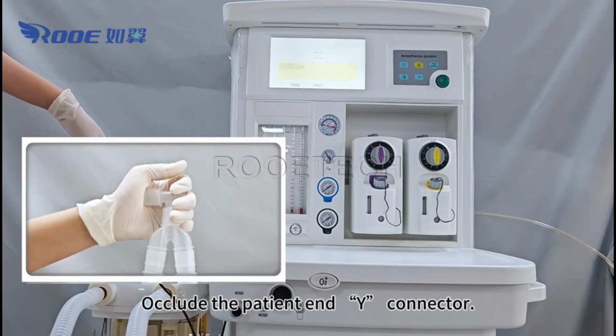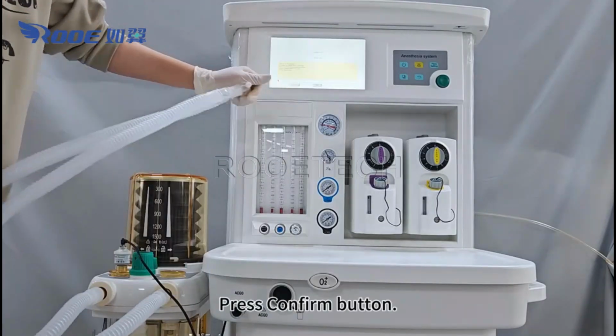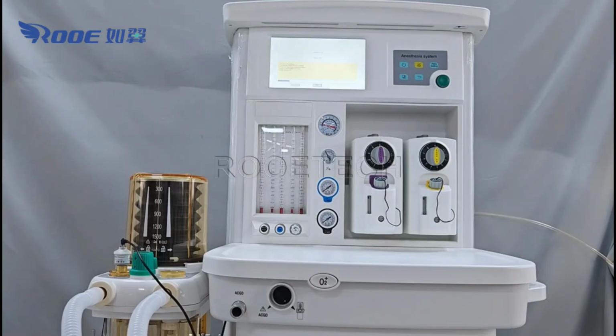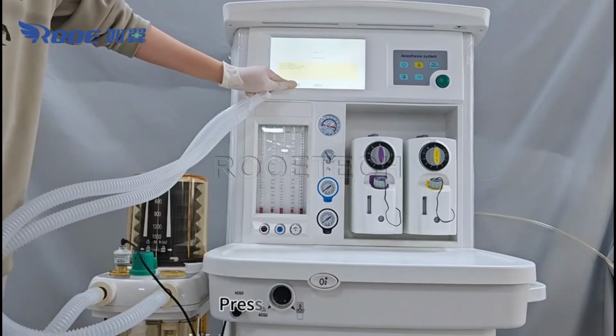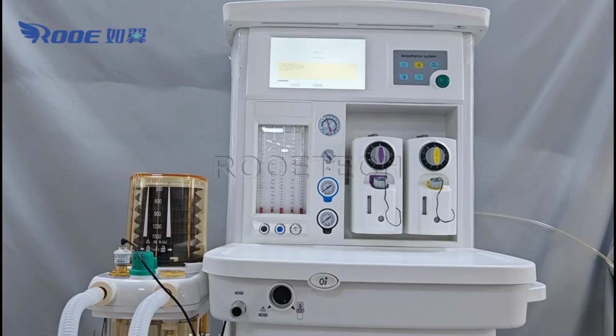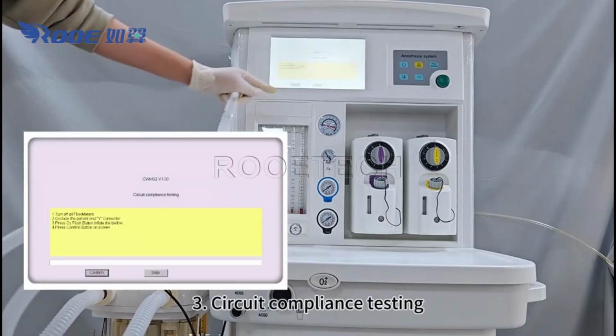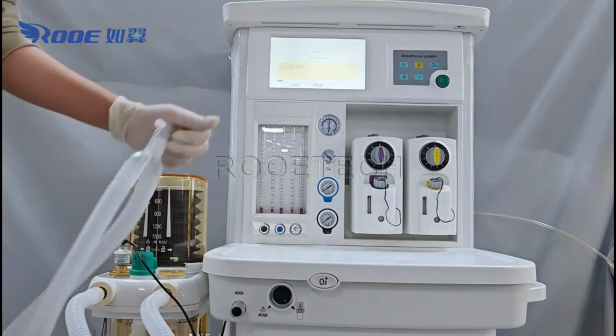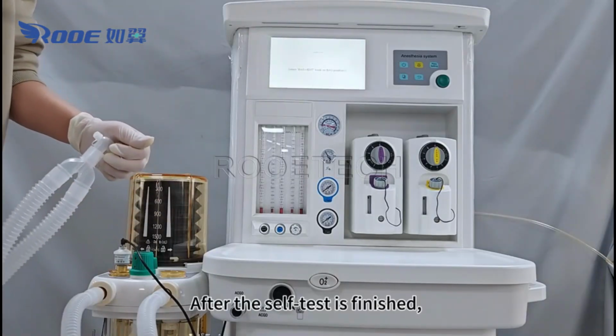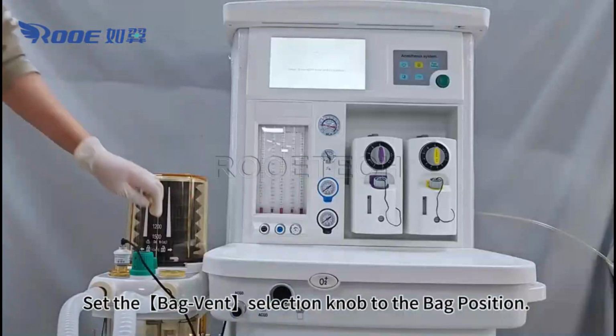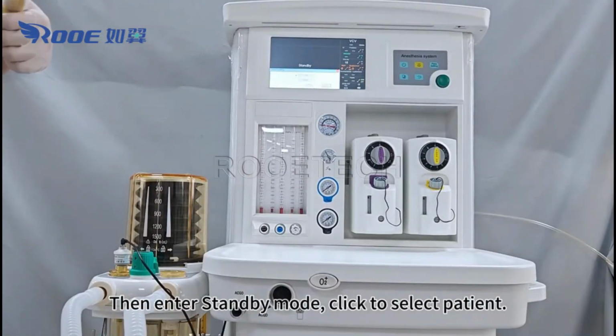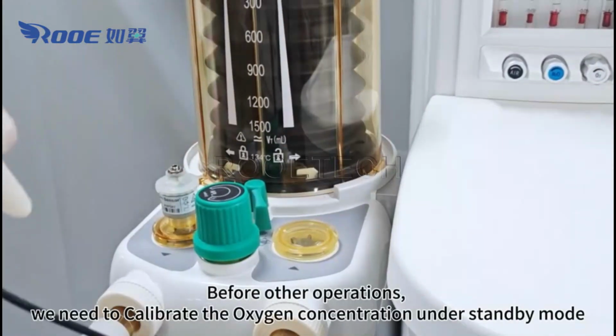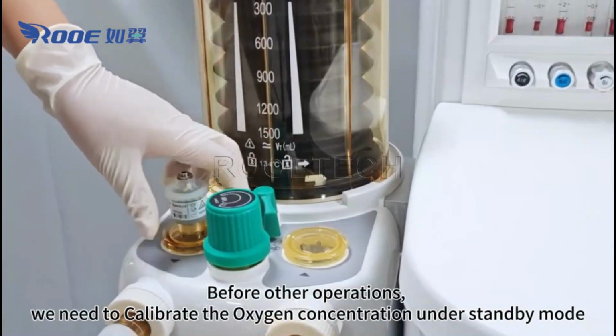Occlude the patient end Y connector. Press confirm button on screen. Second, circuit leakage testing. Press confirm button. Third, circuit compliance testing. Press confirm button. After the self-test is finished, set the bag vent selection knob to the bag position. Then enter standby mode, click to select patient. Before other operations, we need to calibrate the oxygen concentration under standby mode.